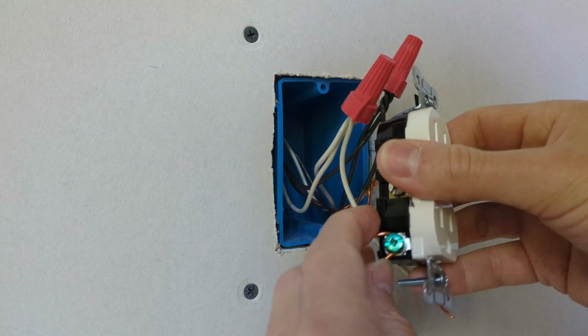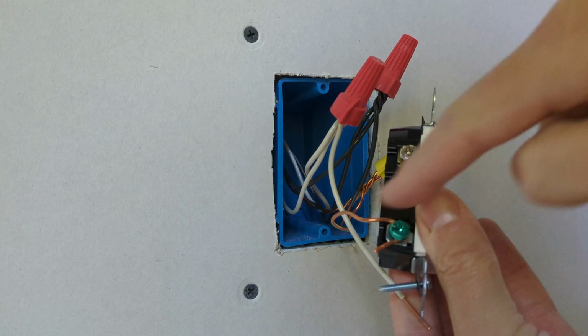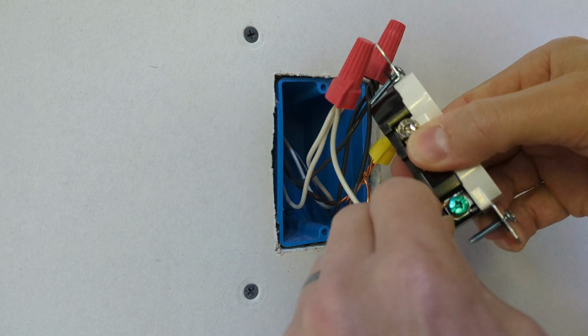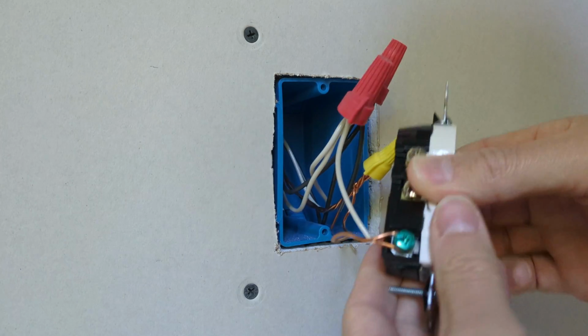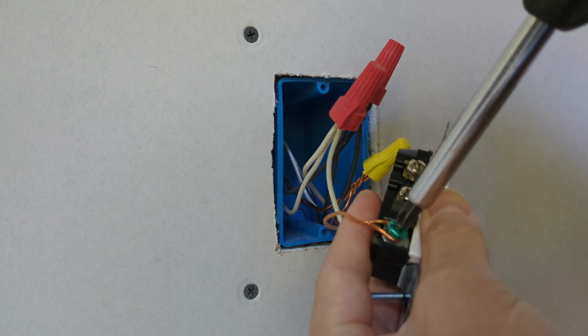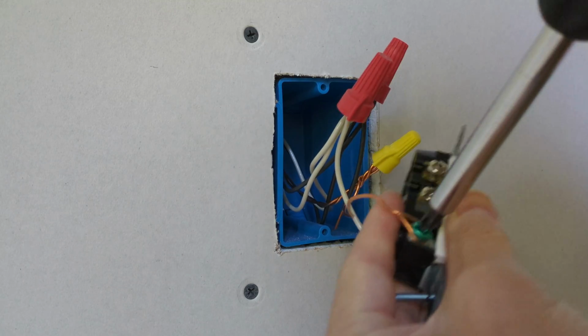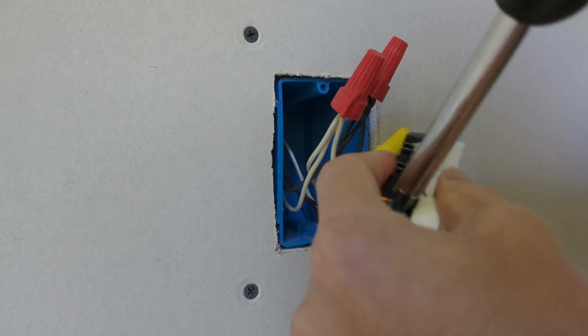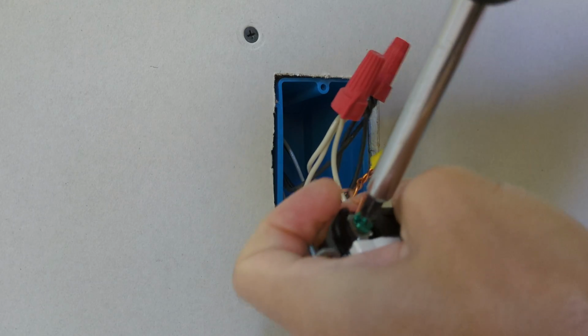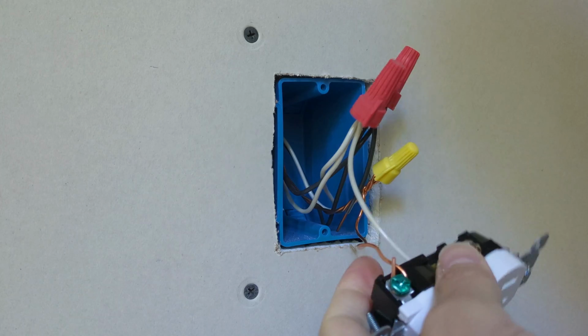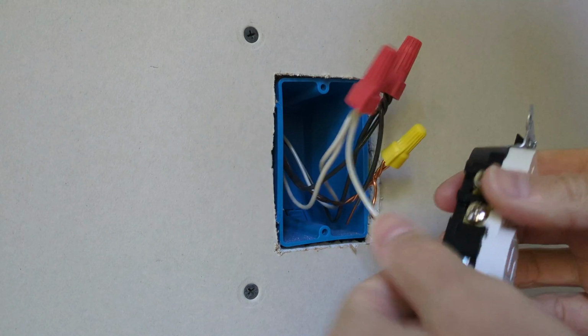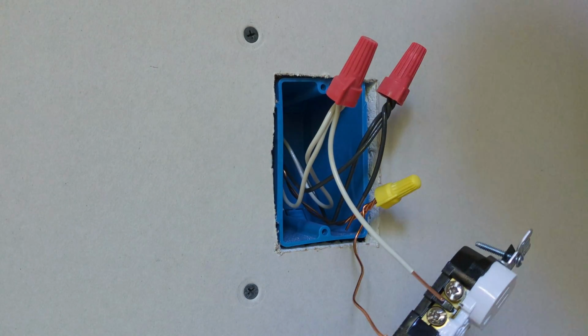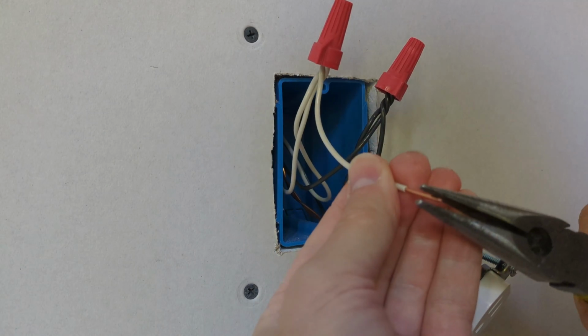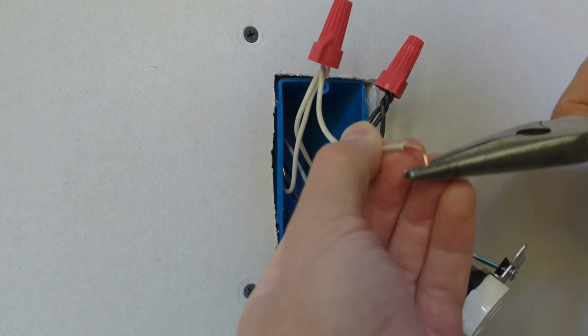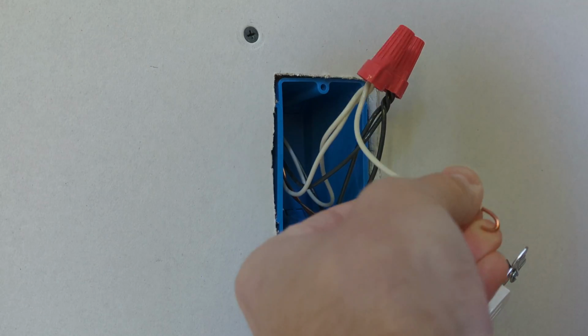So we'll go ahead and connect the ground first. The screw is going to be screwed in clockwise. You want the wire to wrap in the same direction. Got the neutral. This is where I like to use the needle nose pliers. Get that tight turn for going around the screw.